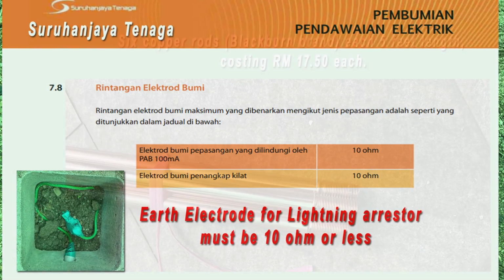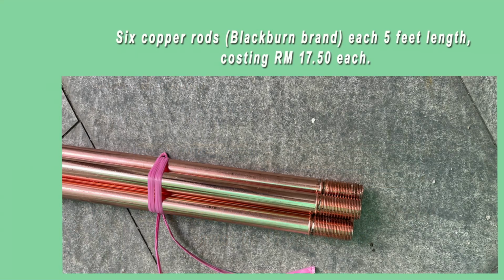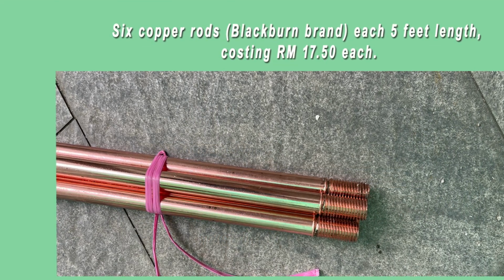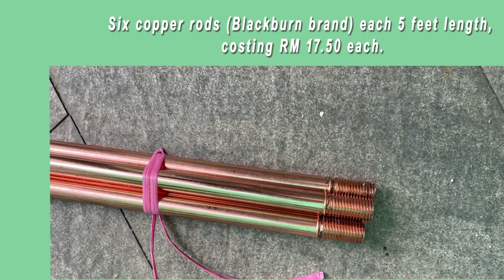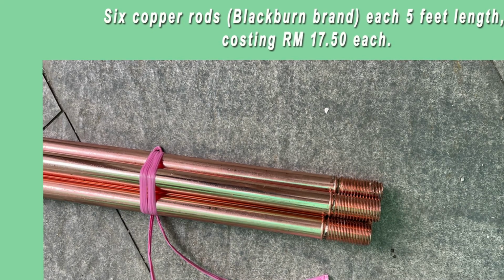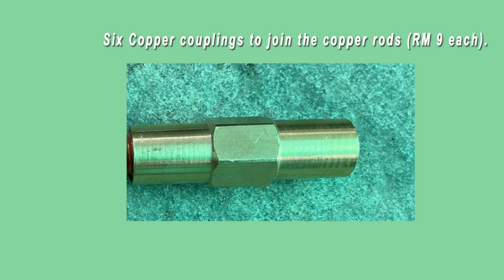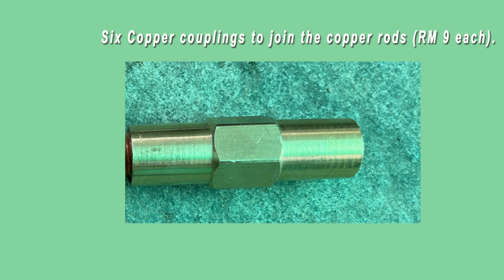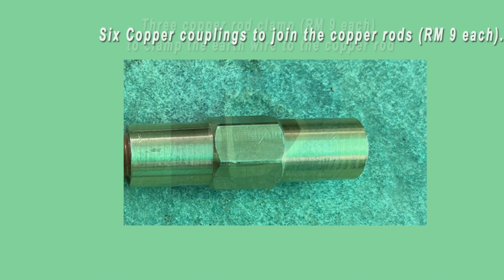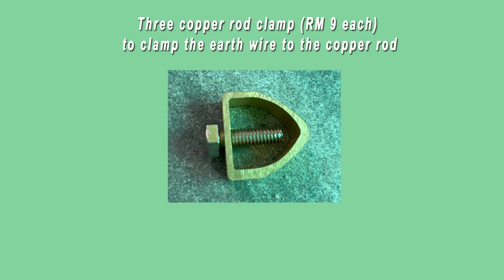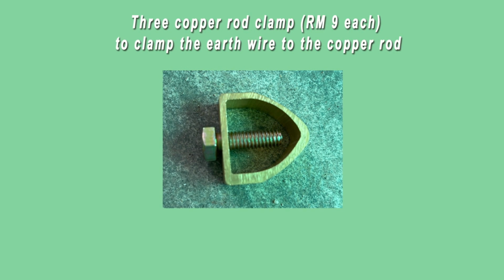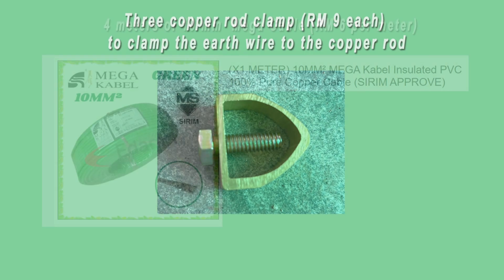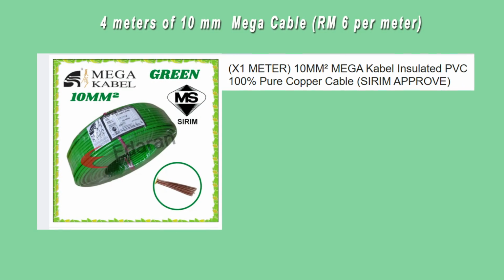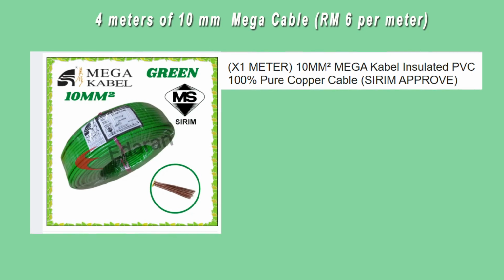10 ohm. This DIY project consists of the following: 6 copper rods, Blackburn brand, each 5 feet length, costing RM 17.50 each. 6 copper couplings to join the copper rods, RM 9 each. 3 copper rod clamps, RM 9 each, to clamp the earth wire to the copper rod. 4 meters of 10 mm mega cable, RM 6 per meter.